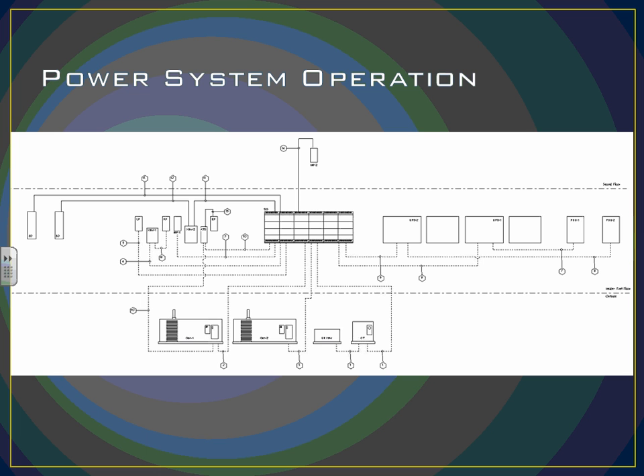Okay. One more, Derek. We're going to put you on the spot, but what happens when the power comes back? Remember when we went to Cummins and how they did it? You want to go over this? Yeah. Power coming back. In that sort of system, when the power starts to come back, it's reaching certain levels. I know with closed transition, when we saw it for Cummins, when it reaches a certain level and negotiates between the two, they're able to close or open the switch again, so that we're switching power back from emergency power and the generator back over to the utility side. And then at that point, you'll be able to hear everything wind down step by step. Once the power load reaches that point, everything will start to go back to the utility side, taking power off the emergency panels, and then switching power and mains and everything back over.